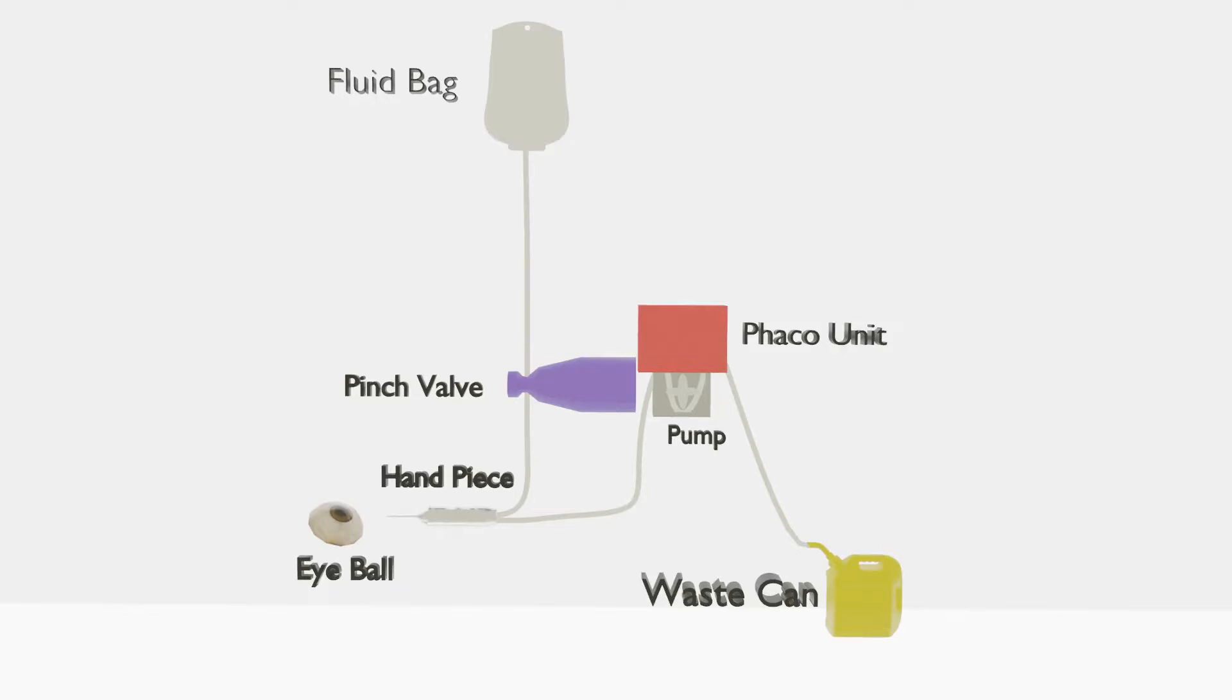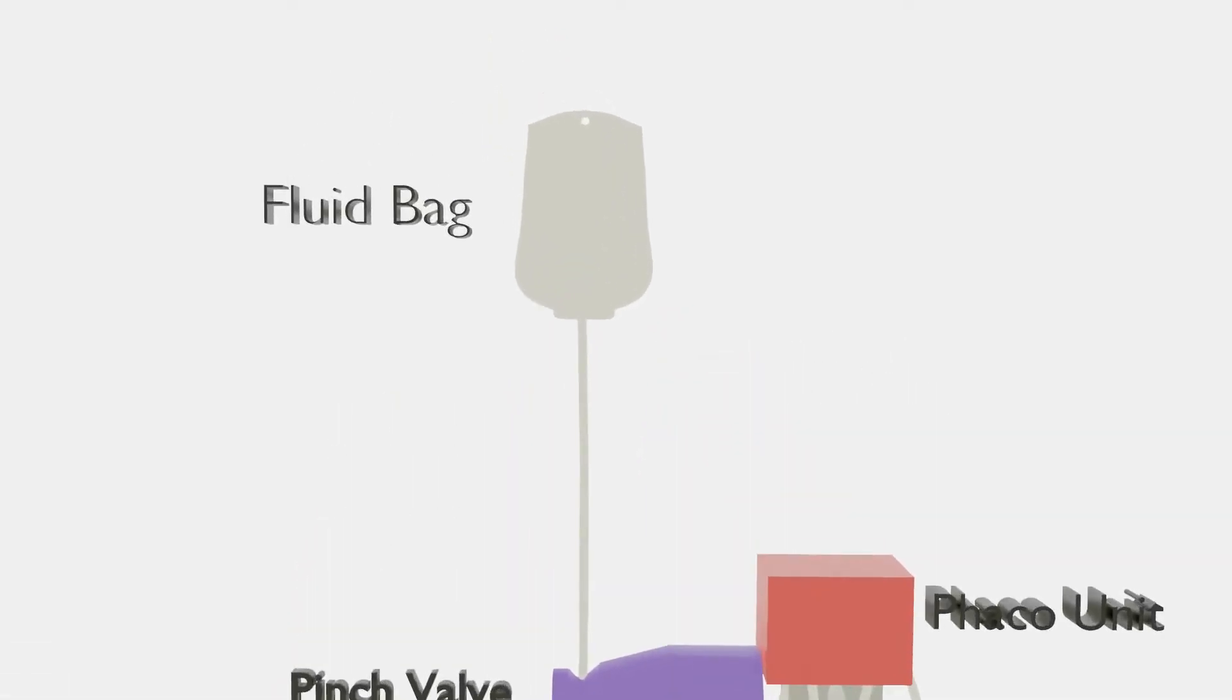First, the fluid bag. They're usually gravity-fed. A bottle of BSS is hung above the patient and gravity provides the input pressure to maintain eye volume during the surgery.